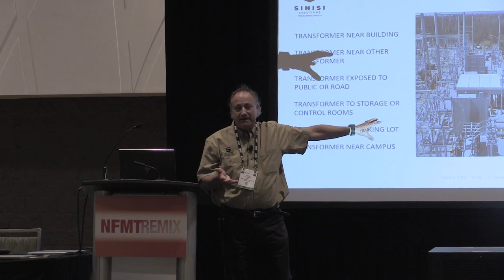Why does a facility need a fire barrier? If your transformers are near a building, say on a university campus where you can see a transformer, you need a fire barrier. In New Jersey, we've got a series of schools with transformers next to them because utilities always use the cheap land next to a school, and kids tie their bicycles to the chain fence. We went to the utility and we're working on fire barriers there to protect the school from the transformers and substation next door.